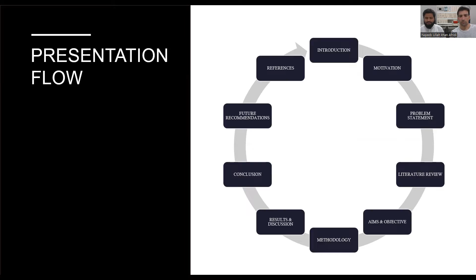Basically, our project is about design and implementation of distance relay for transmission line for laboratory purpose in power system lab. And these distance relays are used to detect fault in transmission line and to determine the distance of fault from the installation point of the relay. Actually, distance relay works on the principle of impedance. So the impedance of transmission line is uniformly divided over its length. For this reason, a distance relay can discriminate with good accuracy between faults that lie in its tripping zone or the ones that are external to its tripping zone.